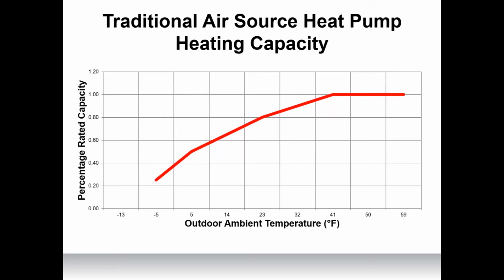As we can see from this chart, looking at a traditional air source heat pump, as the temperature begins to fall, the traditional heat pump loses its ability to provide sufficient heat. Traditional heat pumps, whether they are VRF heat pumps or not, should not be used as a primary heat source here in cold climates. As we start to get down to around freezing temperatures, we drop off significantly, and that's the same for VRF or traditional heat pumps that are not cold climate heat pumps. Would I feel comfortable putting this unit in my home if I'm only getting, say, 20% capacity at -5? Not here in Chicago. I definitely would not feel comfortable. But this is how a traditional air source heat pump works, where here in the Midwest, it's used more as supplemental heating or shoulder season heating.